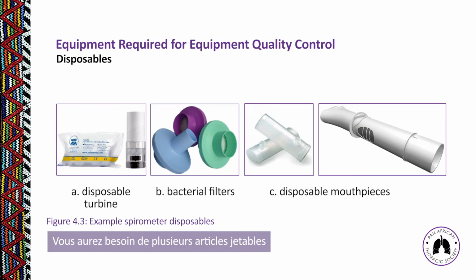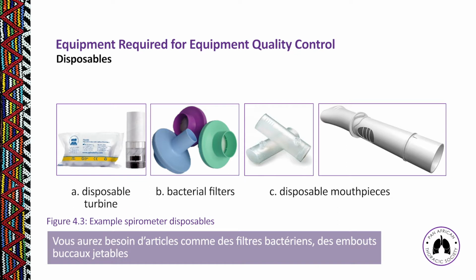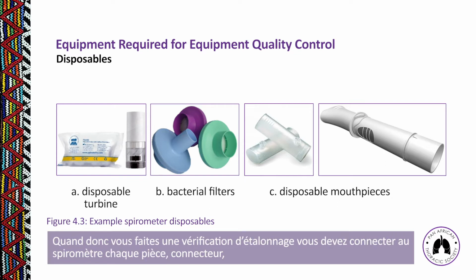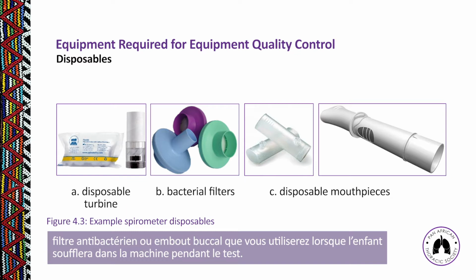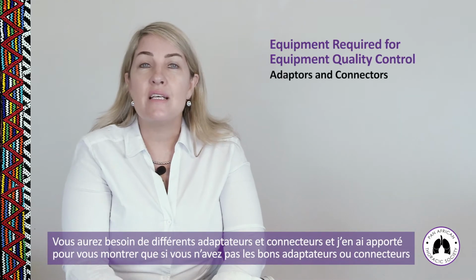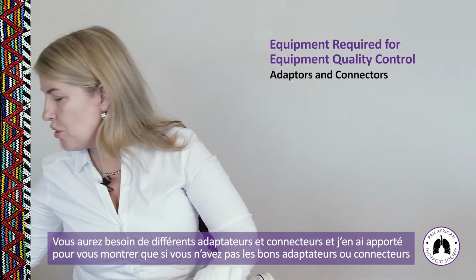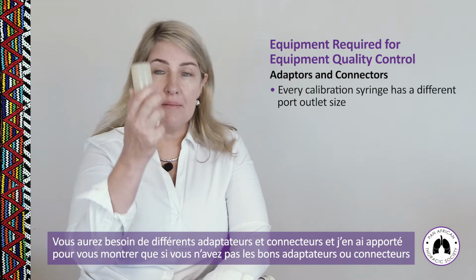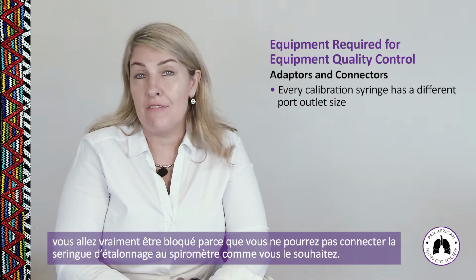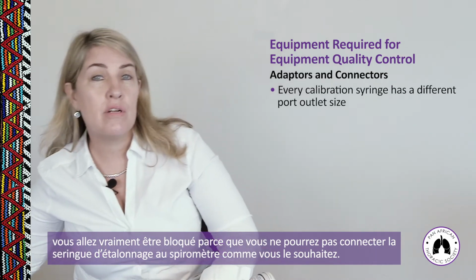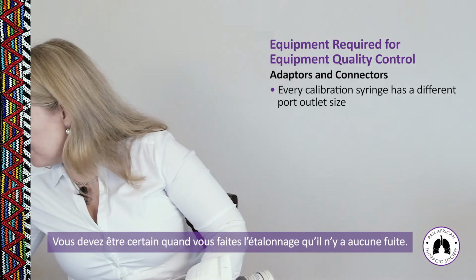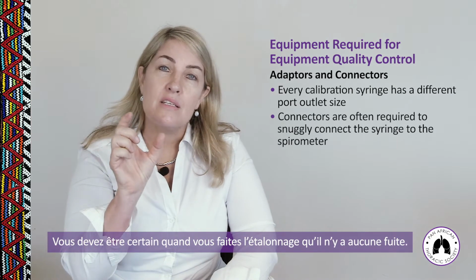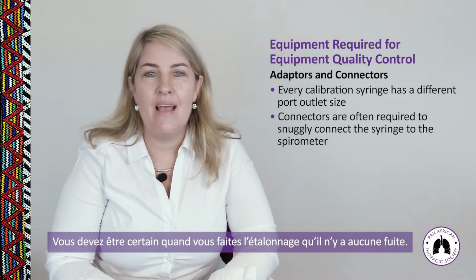You will need various disposables. You will need things like bacterial filters, disposable mouthpieces, and anything else that a child would use when they are actually blowing onto the machine. So when you do a calibration check, you need to attach every part or connector, bacterial filter, and mouthpiece to the spirometer that you will be using when the child is actually blowing on the machine during the test. You will need various adapters and connectors, and I brought a few with me just to show you that if you don't have the correct adapters or connectors, you're really going to be in a fix, because you won't be able to attach your calibration syringe the way you would like to your spirometer. You've got to be sure that when you're calibrating, the connection between the syringe and the spirometer is absolutely airtight and that there's no leaks.